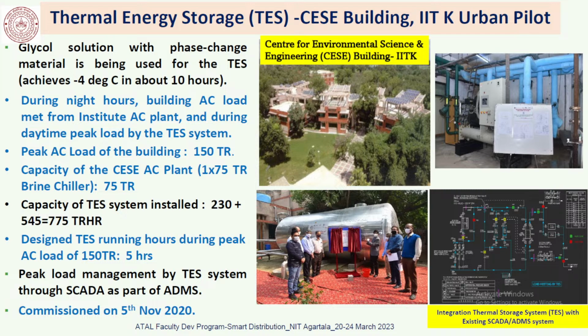During night time when load is less, power from the chilled water supply of the central air conditioning is taken inside the tank, which has a phase change material inserted into it. The property of this phase change material is that even at sub-zero temperature it remains liquid. So the glycol solution with phase change material remains liquid even at -6 or -10 degrees. We cool it to -6 degrees during night time, and during daytime this whole solution supports the chiller operation of the building.